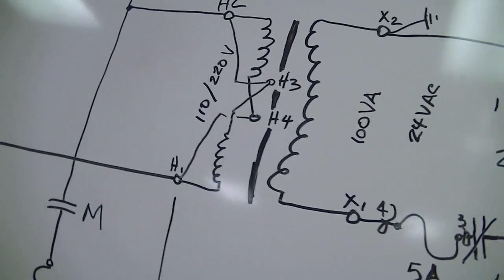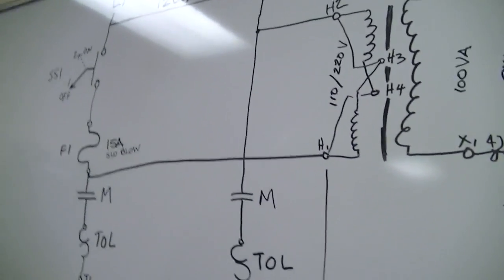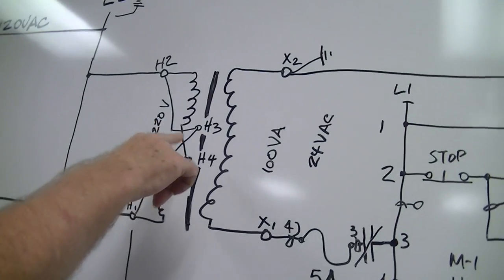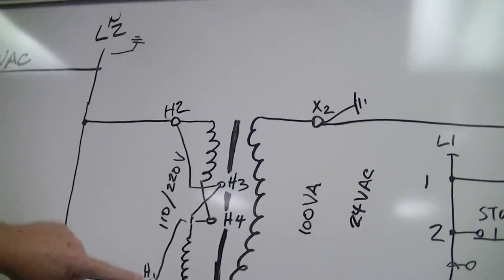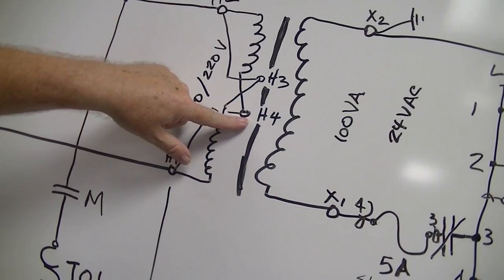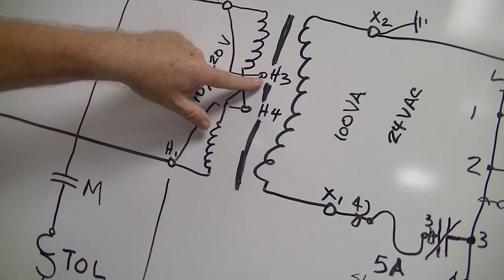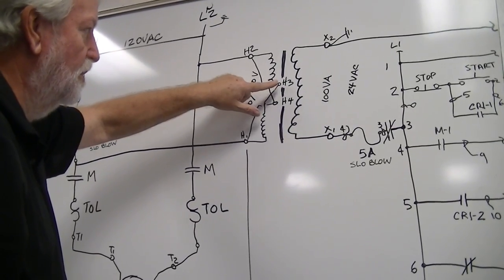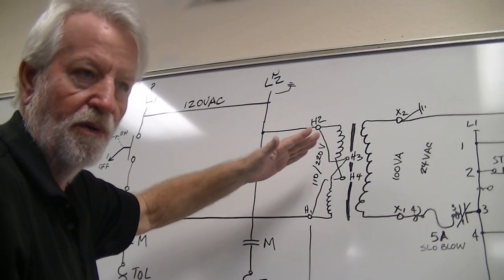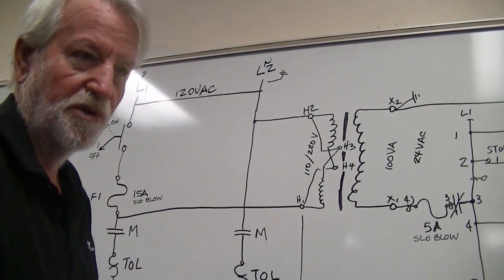In the first one I kind of hem-hauled and decided to back off. I ended up changing it because the way I had it shown was in series. If you look at the actual connections on the drawing — one, two, three, four — this part of the coil comes over to terminal four and this part goes to terminal three. To make them parallel, you put a jumper across one and three, and two and four, which connects them in parallel.